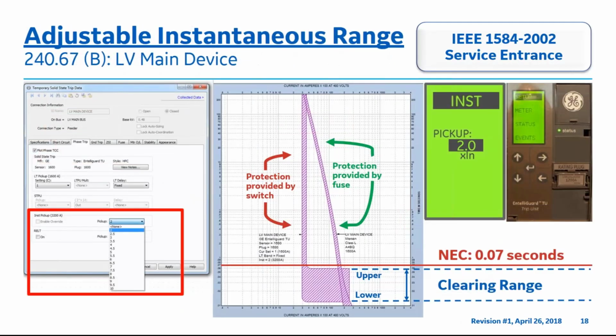With the instantaneous pickup range pull-down menu available, such as in this case, 2.0 is selected on the left-hand side of the screen. It is adjustable from 2.0 to 10.0 for coordination and/or selective coordination purposes. The instantaneous pickup value of 2.0 is labeled on the green screen off to the right. Please notice the specified clearing range of 0.07 seconds is again clearly labeled per the NEC requirements, with the lower and upper clearing time bands marked per the composite instantaneous time current curve shown in the center of the page. On the left, protection provided by the switch, and on the right, protection provided by the fuse.